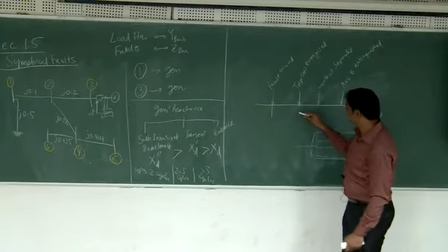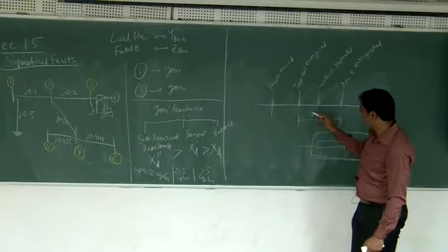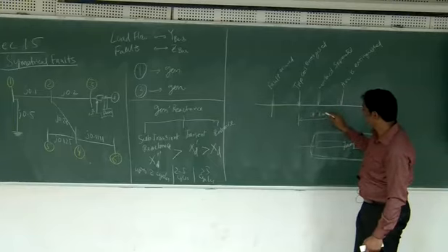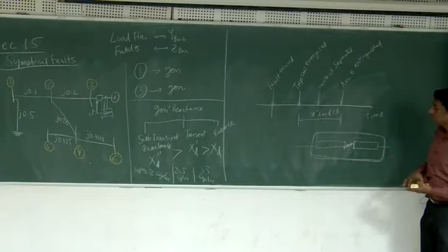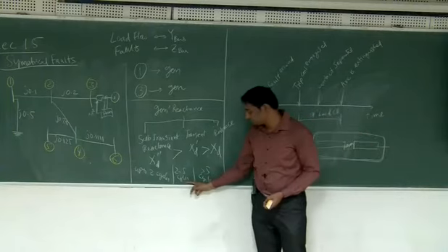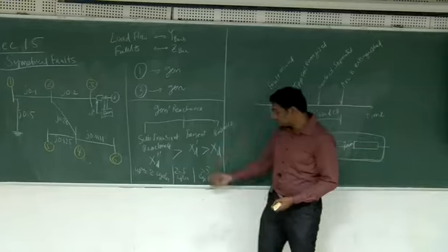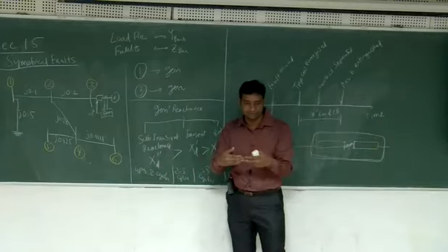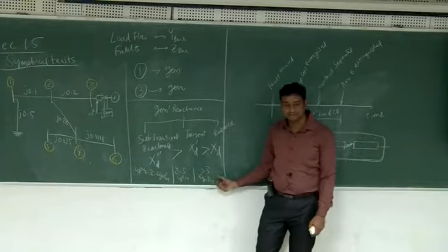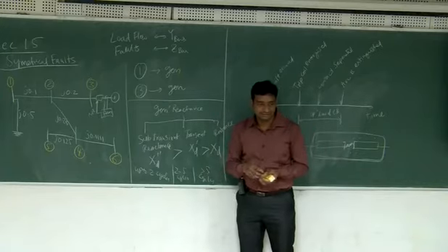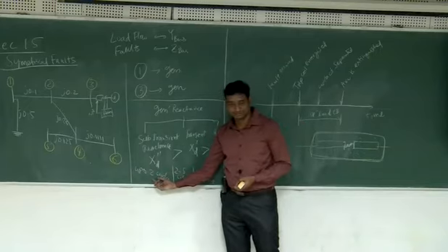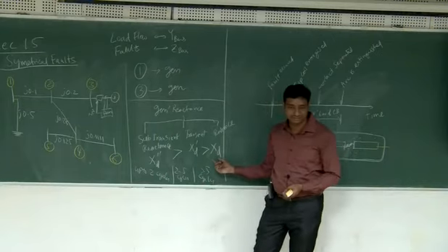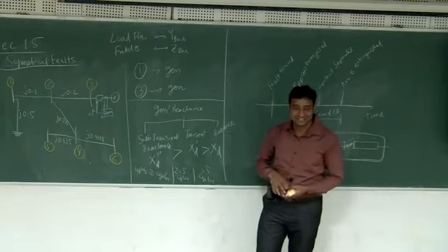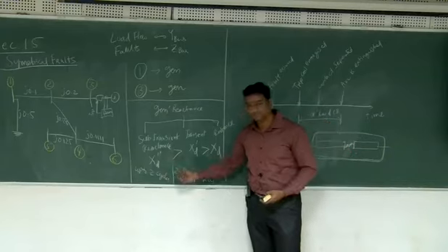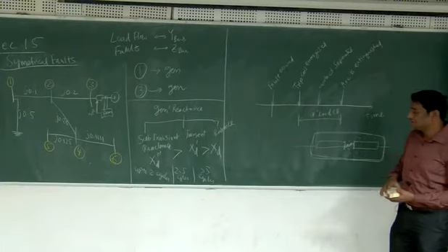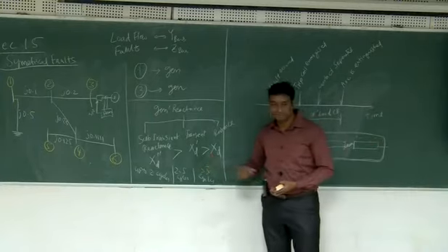So the time between these two is the operation time of the circuit breaker. Now the operation time of a circuit breaker is somewhere maybe between 2 to 5 cycles. So this XD double dash is already present while the circuit breaker is still closed, and sometimes the circuit breaker operates even after this. So if I want to do fault calculation, I should use this value. And if I want to do the regular load flow calculation, I should use this value, XD. All this history is only for that small point, that whenever you are doing the fault calculation, you have to use this one. The manufacturer of the machine will specify these three values separately. Okay.